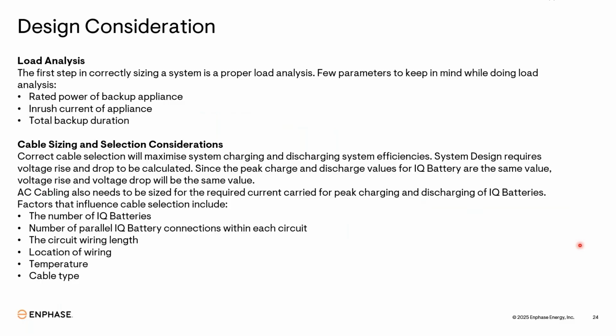Even the homeowner is not aware of it, so he simply says I want this, because he's not aware how backup works. If you calculate 30 kilowatt multiplied by 8 hours, you have 240 kWh of energy. See how many batteries you will need to meet 240 kWh. 240 kWh multiplied by 5, you need that many batteries. See how big the battery bank will be. A complete room would be occupied with batteries. You need more than a room of space.